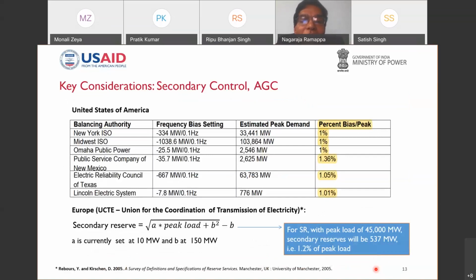Now, let us also see what is being talked about for secondary control, or the AGC. In America, New York ISO talks about a frequency bias setting of 334 megawatt per 0.1 Hertz, and an estimated peak demand of 33,441 megawatt. Therefore, the percentage bias for the peak is about 1%. Like that, the different ISOs have given. What is very important to understand is that even though the percentage is more or less the same, the quantum depends upon the base load or the peak demand.